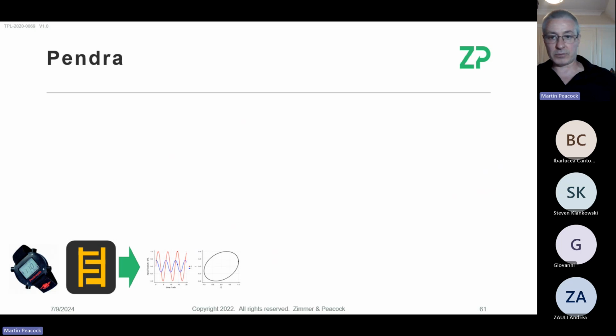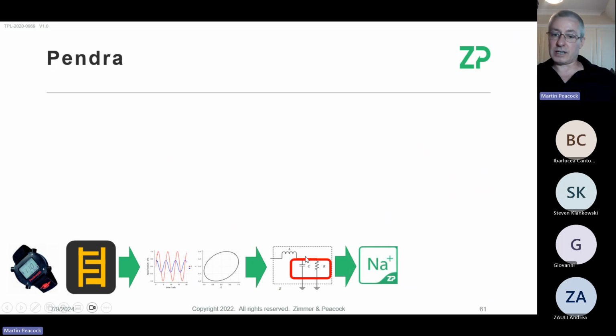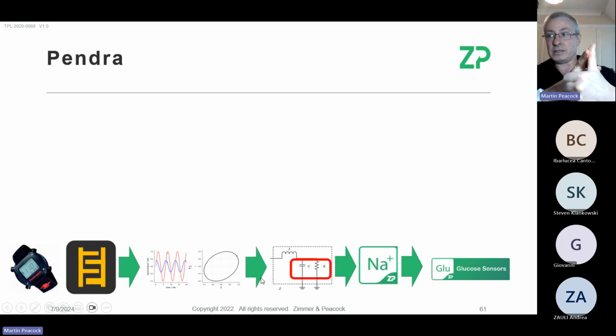Electrochemical impedance spectroscopy was a term I threw out earlier on, something I'm very familiar with. They were actually measuring, they think, the sodium levels, and then they were saying that the sodium levels were linked to glucose levels. So that means their primary signal was impedance, from which they think measuring sodium, and the sodium was linked to glucose. So that's a primary signal, that's a secondary signal, and that's a tertiary. So they were very separated from the thing they were actually trying to measure. And that's why they probably ended up with that accuracy.